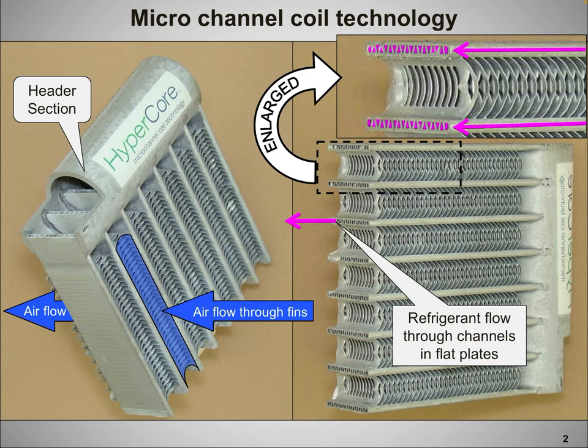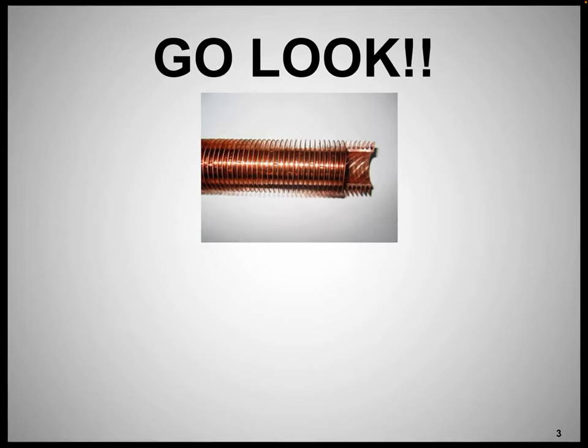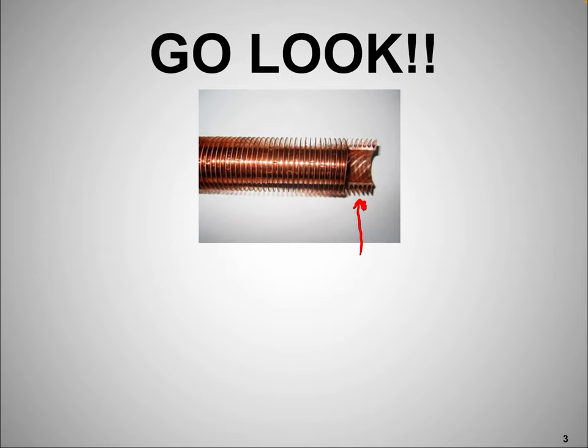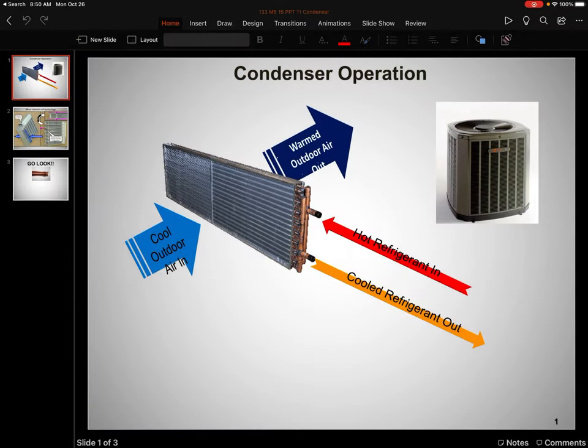The biggest reason for microchannel condensers is that they can utilize so much less refrigerant within the system, but there are some downsides — the charging of these units is much more critical. Instead of round tubes, they have passageways that allow the refrigerant to flow through little plates. Here's a more traditional condenser — you can see all these little fins. They call it an enhanced copper tube, which has so much more surface area and better heat transfer than a plain round copper tube.